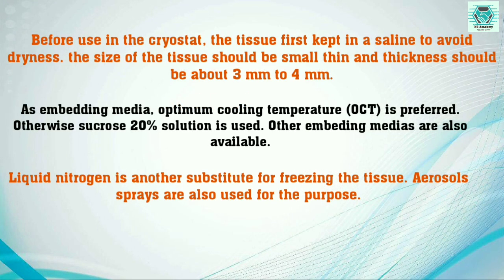Before using the cryostat, the specimen should be handled properly. The tissue must reach the histopathology lab immediately to avoid drying; it should be kept in saline. The size of the tissue should be small and thin so that good smooth sections can be obtained and freezing is also quick. The thickness of the tissue should be about 3 mm to 4 mm.